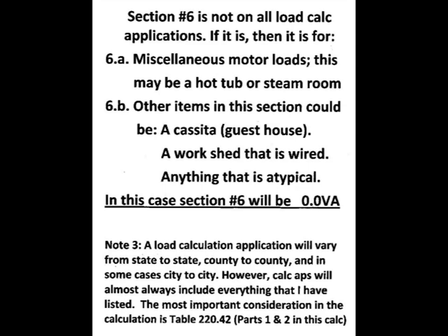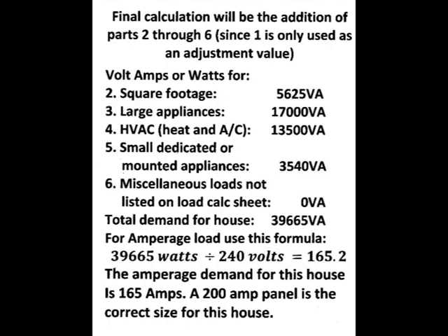Section 6 is not on all load calc applications. If it is, then it is for miscellaneous items like motor loads, a hot tub, maybe a steam room, a casita which is a guest house, or a work shed that's wired. In this case, section 6 will be 0 volt amps. The final calculations will be the addition of parts 2 through 6, since section 1 is only used as an adjustment value of the 35% minus the first 3,000. The total demand is 39,665 volt amps or watts.